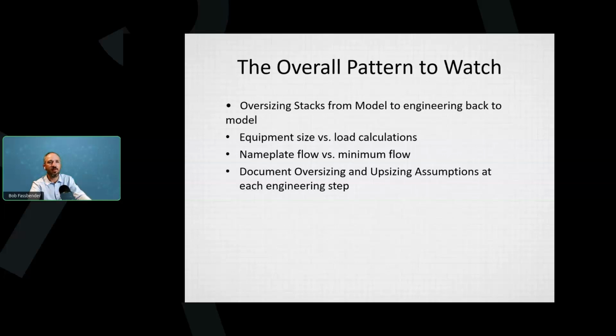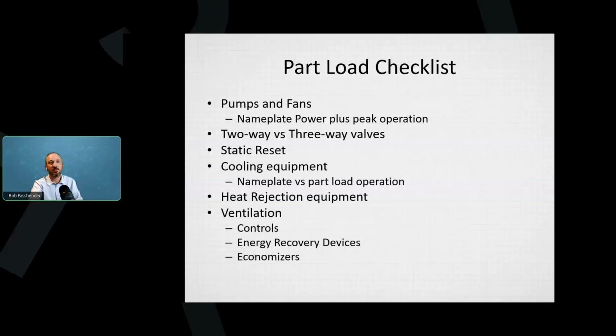If you added a safety factor and it pushed you into the next size category of an item, you should have that documented. For example, we oversized this by 15%, and now it's 3% over the size of this. Maybe you don't want to upsize it, because right sizing saves a ton of energy and a ton of capital cost. I could give probably a 3-hour set of slides on why right sizing saves energy outside of the capital cost. So here's a checklist of some items that you want to verify.